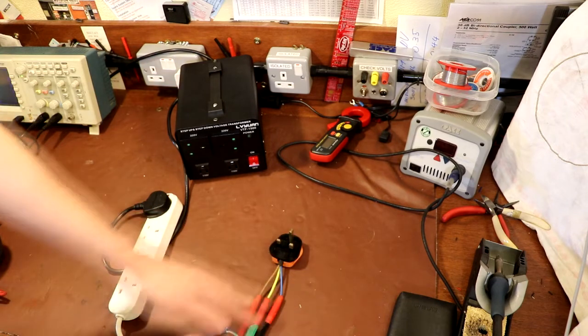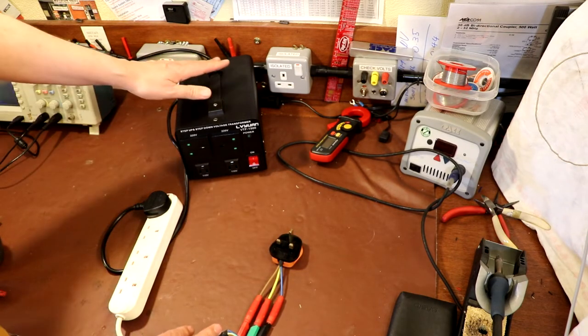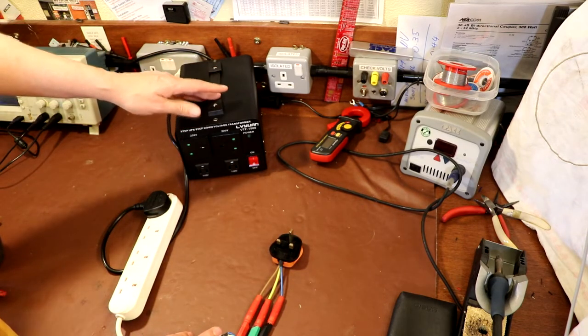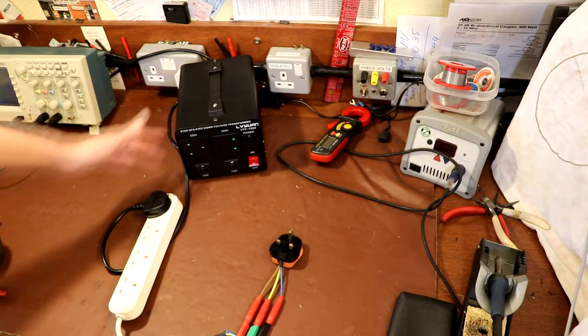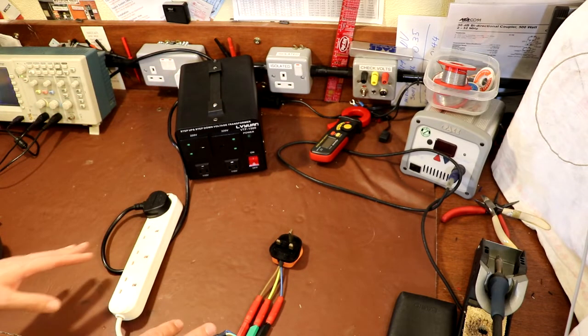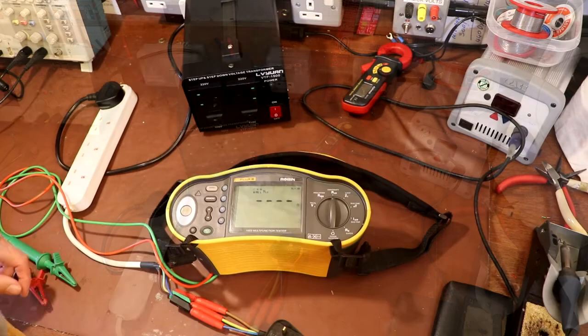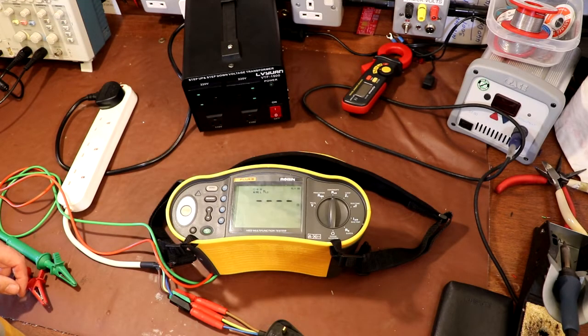What I'm going to do is measure the resistance of this, so I'm not just measuring the resistance of the transformer primary, I'm also measuring the resistance of our wiring, and it's probably going to be quite a low reading. So to measure the resistance of our primary circuit, we're going to use this Fluke meter, and this Fluke meter is a little bit special in that it's designed to test electrical installations, so it has some rather specialist functions that you wouldn't find on a normal bench meter.